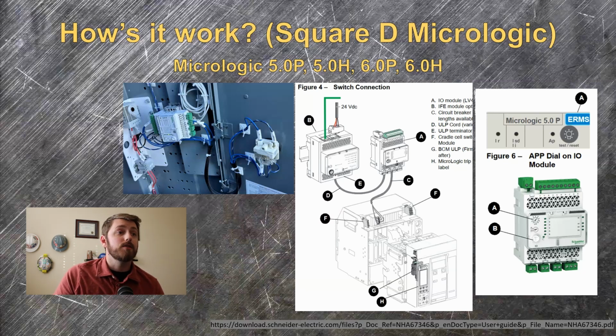Since it's a communication function, you have to make sure that the trip unit is turned on and networked properly. A quick tip on those, if it looks like everything's wired up right, power's on, and you're getting the switch input to the IFE module, you have to hold down the T button on the IFE module for 5 seconds. It forces the IFE module to try to reconnect to the trip unit, and every time I've had an issue with it, hold the button down, it works fine.